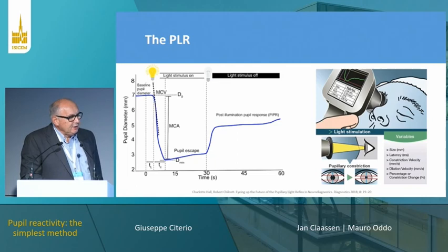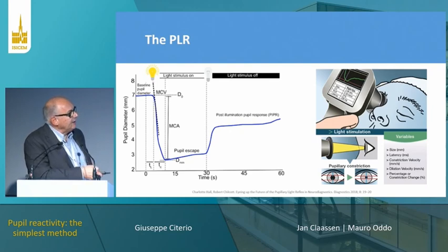So on the market, 2 devices came out, because the technology with a standardized, very high intensity light on the retina of the patient will produce the reaction of the pupils, but we can record many parameters that the nurses could not record. The exact baseline pupillary diameter, the velocity of constriction, the maximal constriction of the pupil, and the escape of the pupil afterwards.